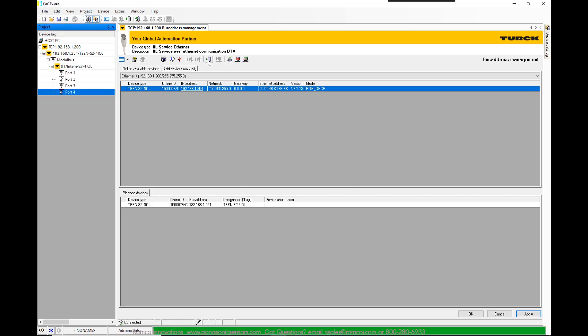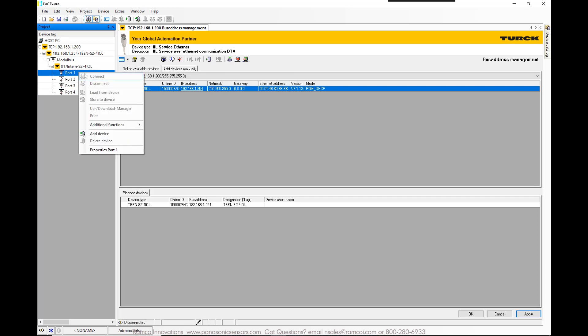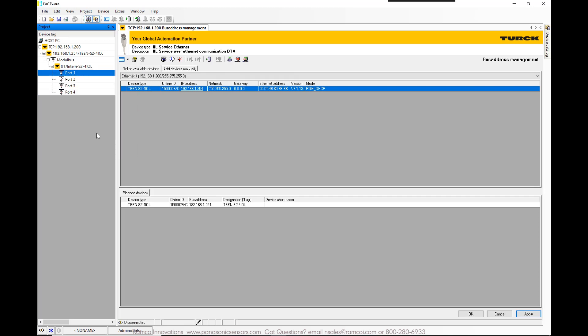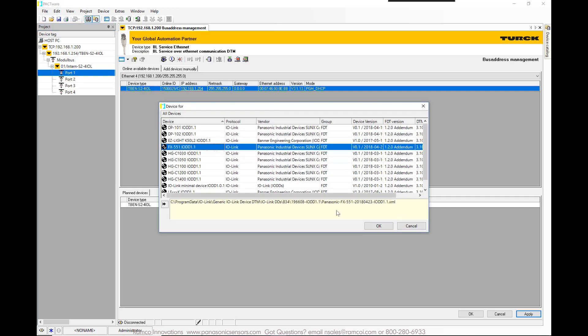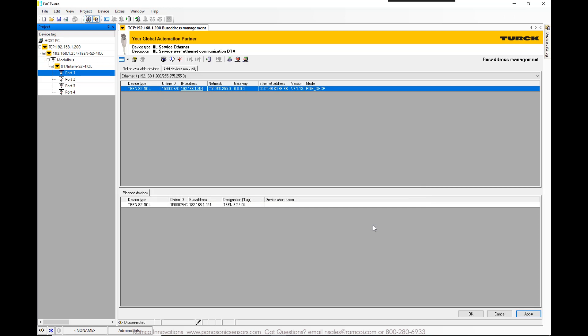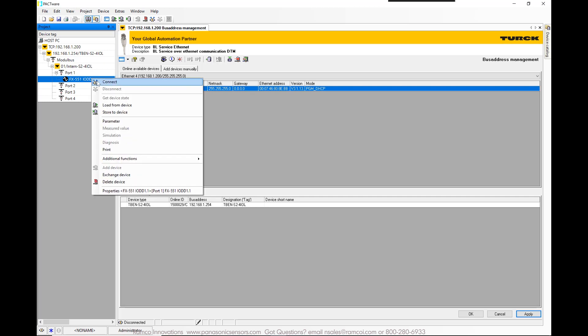Once you're connected to the IO-Link master, you right-click on the port that you connected the sensor to and select add device. This is where you select the IO-DD file for the device that you are connected to. Again, I added the IO-DD file previously. You then hover over the IO-DD file, right-click and select connect.